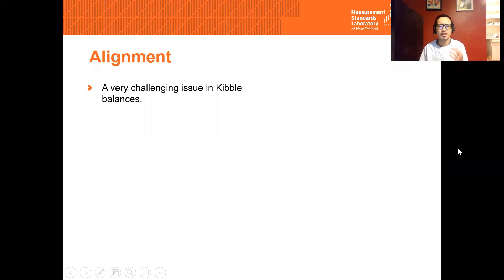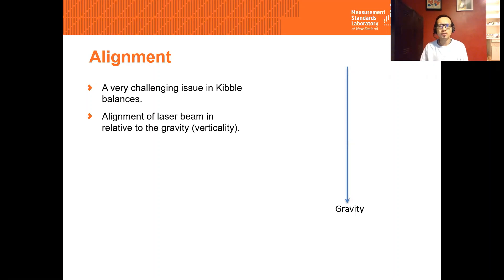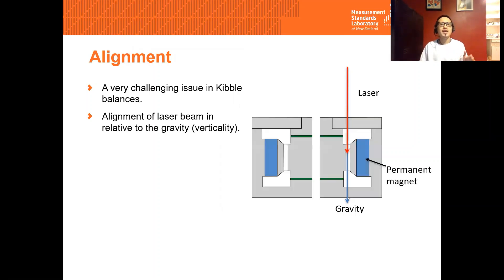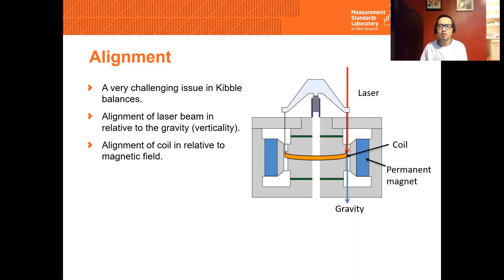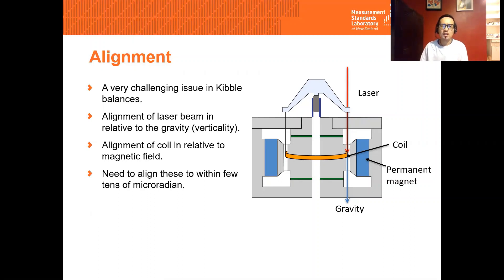One of the most challenging issues that any Kibble Balance can face is the issue of alignments. We are currently experimenting with different techniques to carefully address them — for example, how to ensure the laser for measuring the velocity of the coil is aligned to gravity, which is always pointing in the vertical direction. Any misalignment of the coil relative to the magnetic field will cause the coil to tilt. Any of these misalignments will produce measurement errors and increase the overall uncertainty significantly.